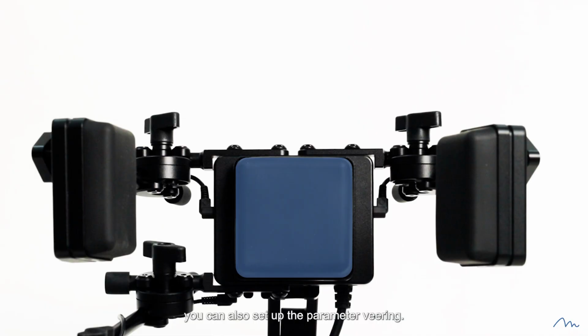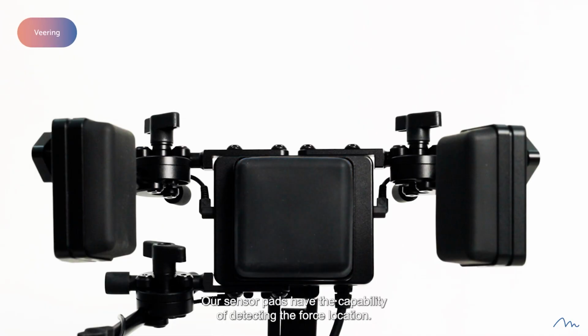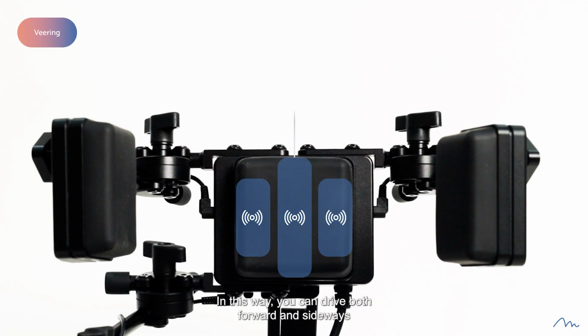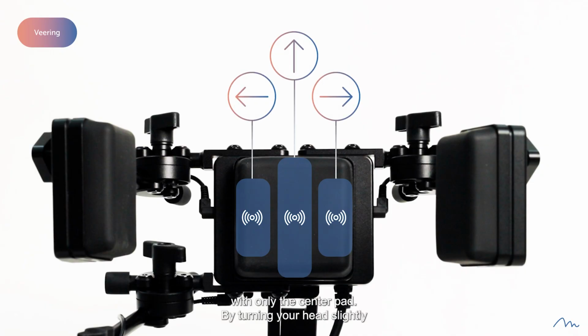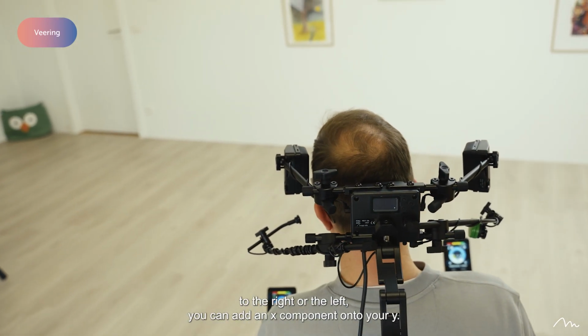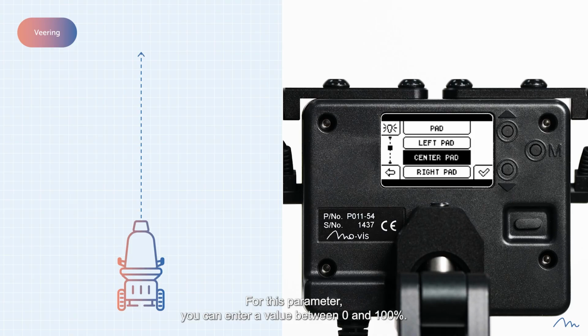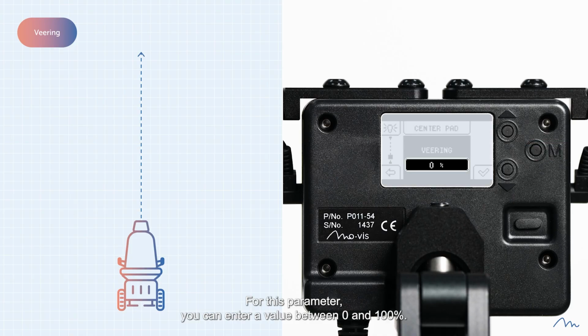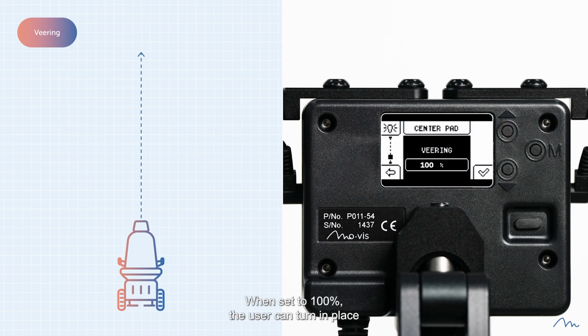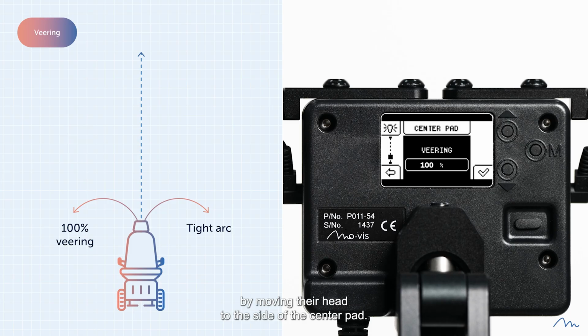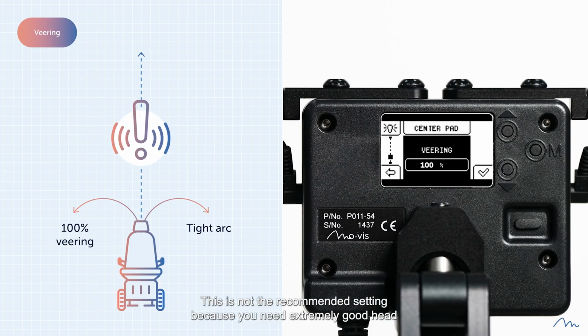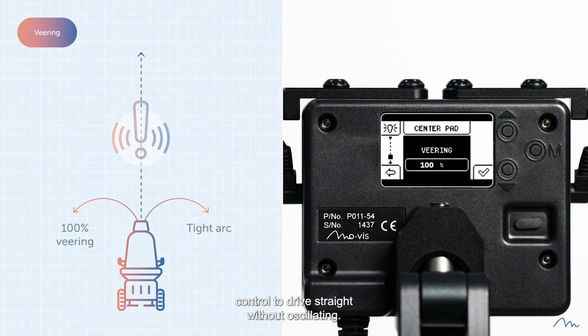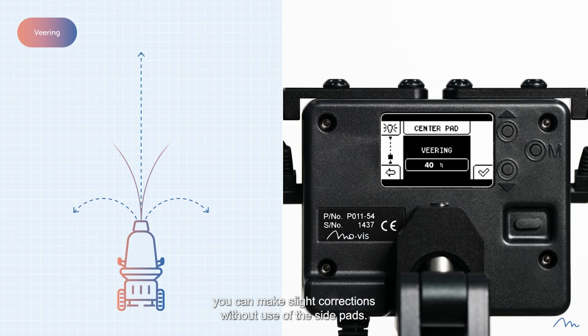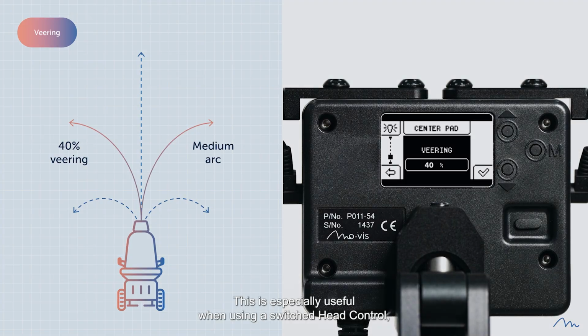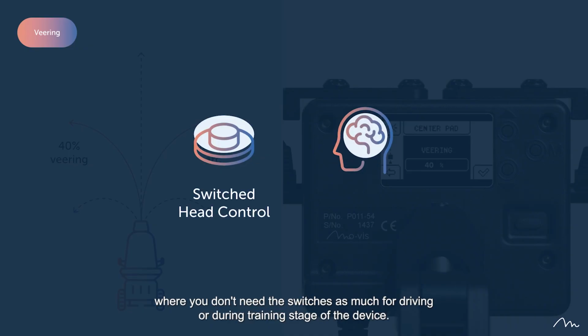For the center pad, you can also set up the parameter veering. Our sensor pads have the capability of detecting the force location. In this way, you can drive both forward and sideways with only the center pad. By turning your head slightly to the right or the left, you can add an X component onto your Y. For this parameter, you can enter a value between 0% and 100%. When set to 100%, the user can turn in place by moving their head to the side of the center pad. This is not the recommended setting because you need extremely good head control to drive straight without oscillating. However, if you set it to 40%, for example, you can make slight corrections without use of the side pads. This is especially useful when using a switched head control, where you don't need the switches as much for driving or during training stage of the device.